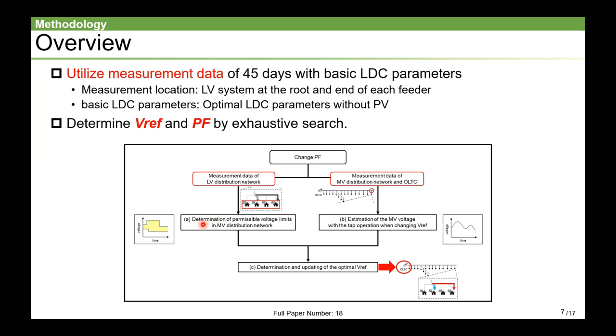First, in step A, the permissible voltage range of MV nodes are determined from every customer's voltage information. Next, in step B, we estimate how the MV voltage would behave if the values of Vref were changed. Finally, in step C, we determine the parameters that voltage at measurement points is least likely to violate by exhaustive search. From the next slide, each step will be explained in detail.